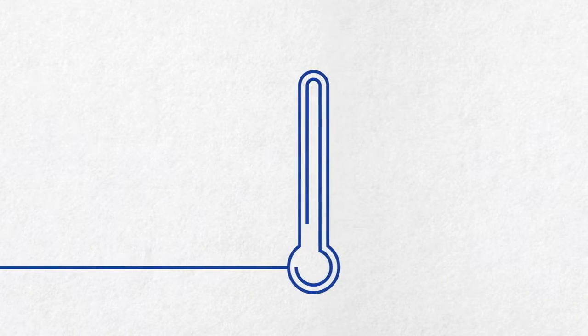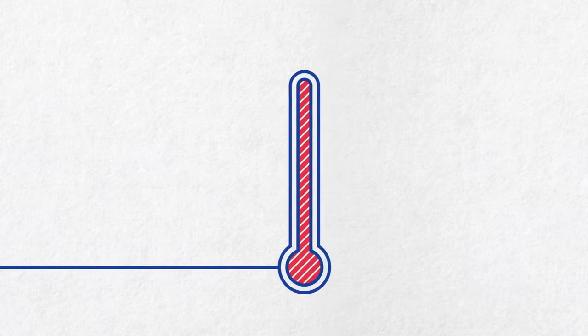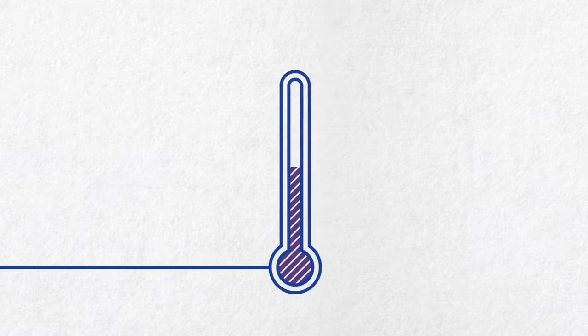Hard to say for sure. The vibration readings we saw didn't indicate an issue, but when the bearing temperature climbed over 230 degrees, we brought her down.